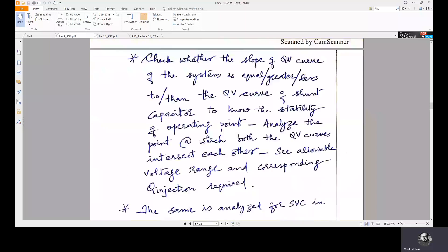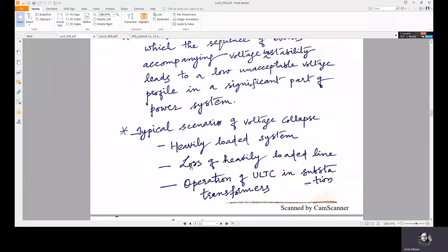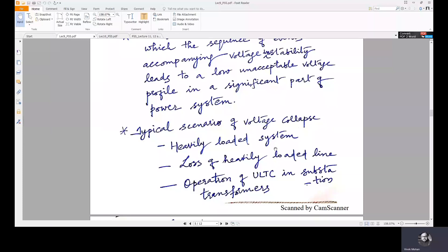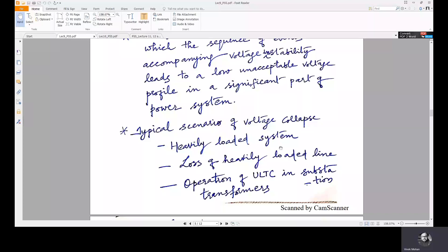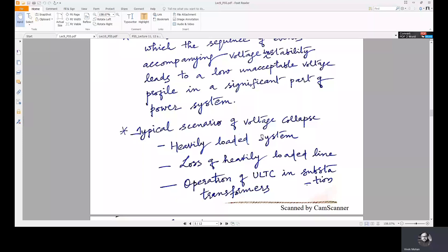Now we will move on to the analysis of voltage collapse. A typical scenario of voltage collapse can occur due to a heavily loaded system, where more current flows through the lines, increasing the I²X reactive power loss and the IX voltage drop, making the receiving end bus voltages vulnerable and the system prone to voltage collapse.